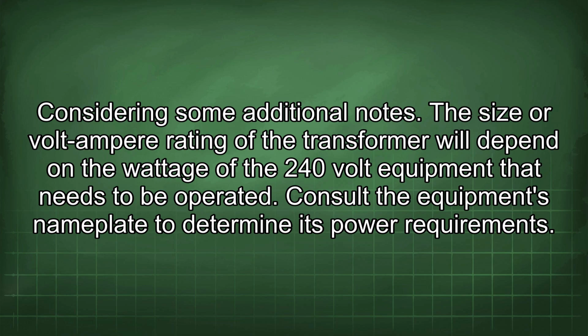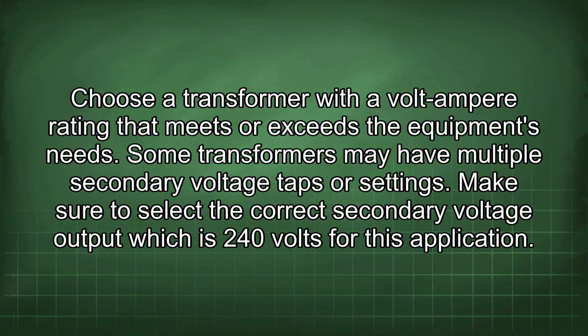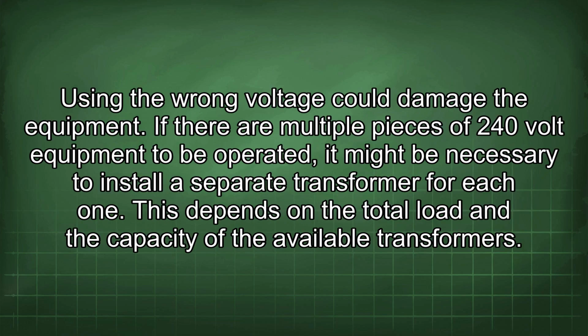Considering some additional notes. The size or volt-ampere rating of the transformer will depend on the wattage of the 240-volt equipment that needs to be operated. Consult the equipment's nameplate to determine its power requirements. Choose a transformer with a volt-ampere rating that meets or exceeds the equipment's needs. Some transformers may have multiple secondary voltage taps or settings. Make sure to select the correct secondary voltage output, which is 240 volts for this application. Using the wrong voltage could damage the equipment.